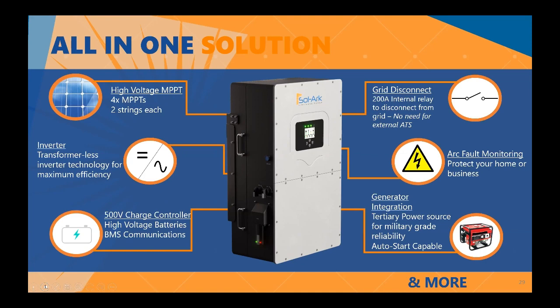And as well, you can use this port in the Sol-Ark to AC couple into the inverters. You can use another string inverter, microinverters, a generator, or basically, I think that would be the most common usage for this port. Another important aspect is the arc fault monitoring. The Sol-Ark will throw an arc fault if the current suddenly spikes in order to protect the system, and it will require the installer or the homeowner to erase this fault in order for the Sol-Ark to start producing power again.